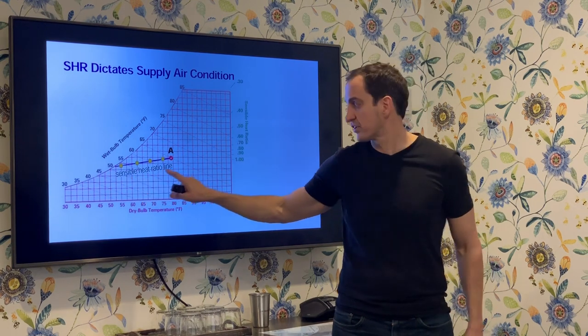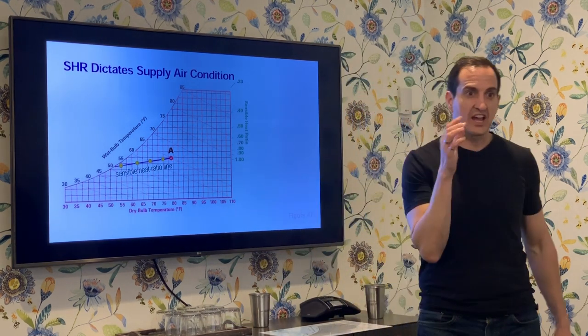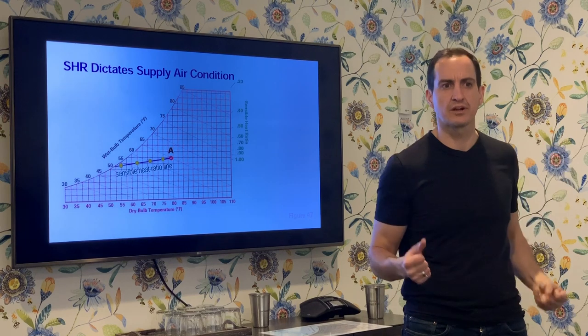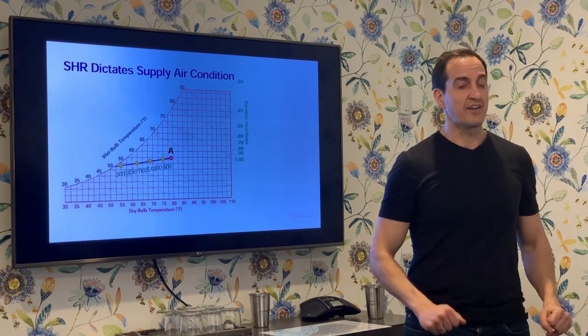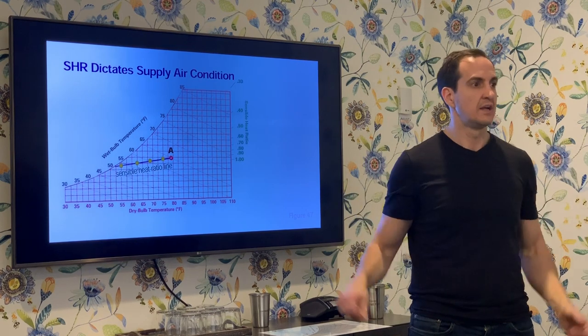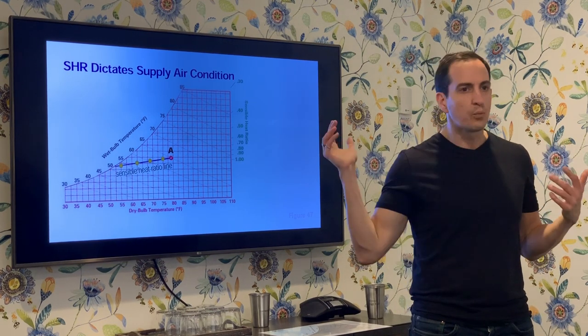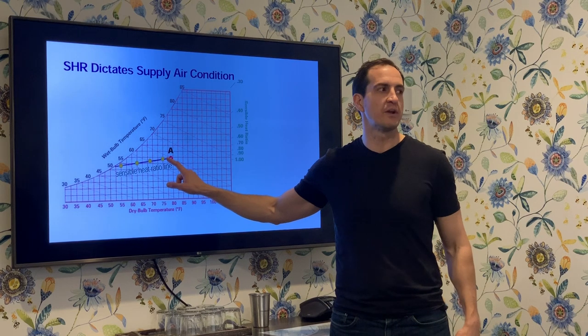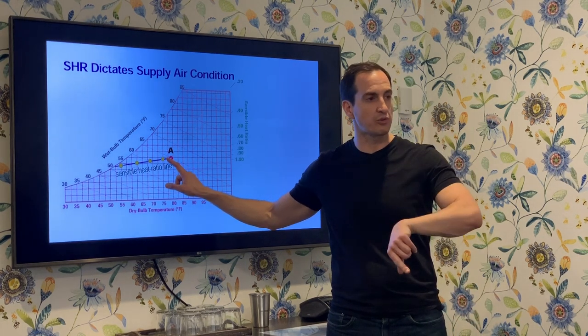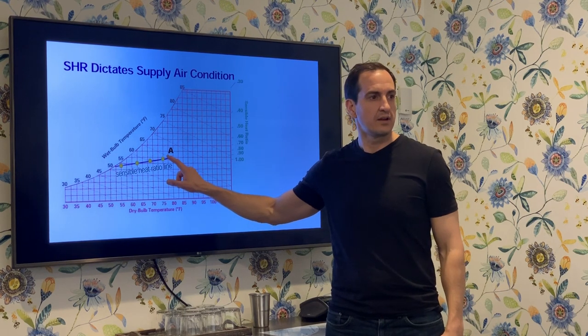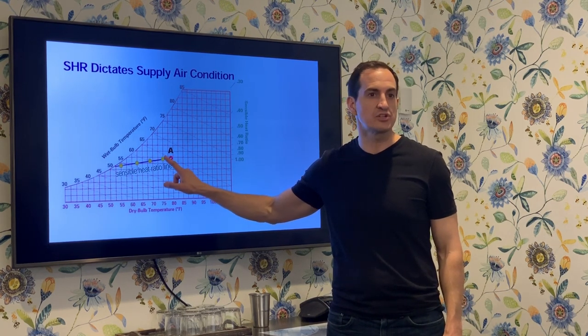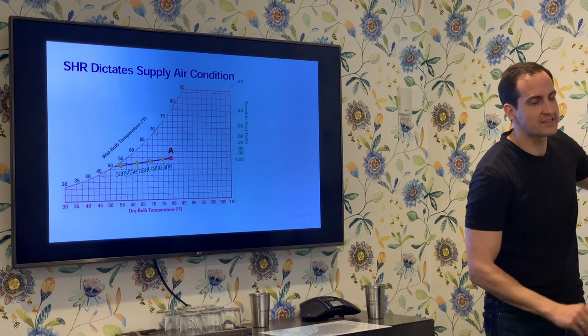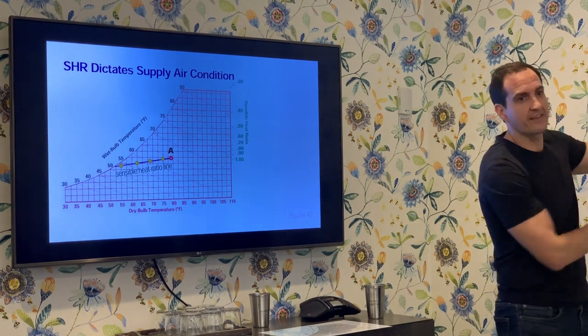I could take all the air in this room and, wanting to keep it at 70°F and 50% relative humidity, blast air through like a tornado, taking away just a little bit of energy with each pass — changing temperature and humidity only a small fraction before reintroducing it. Alternatively, if I used a tiny tube to condition a small amount of air, I would need to make that air very cold and very dry to get rid of all the heat and humidity being generated.